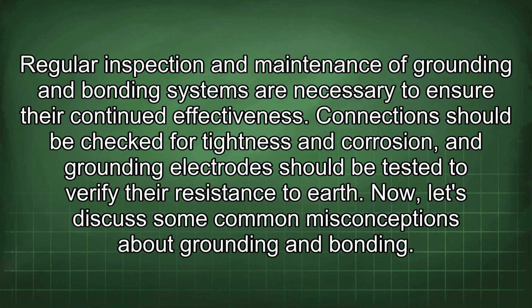Regular inspection and maintenance of grounding and bonding systems are necessary to ensure their continued effectiveness. Connections should be checked for tightness and corrosion, and grounding electrodes should be tested to verify their resistance to earth. Now let's discuss some common misconceptions about grounding and bonding.